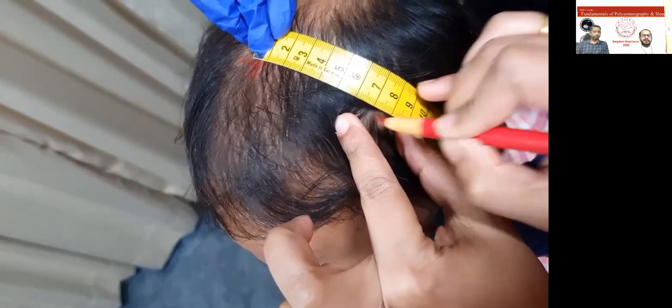As you can see, the total distance was roughly 38 centimeters, and 20% of 38 centimeters will be 7.6 centimeters. So from that initial intersection point Cz, we will measure 7.6 centimeters and use a small sketch pen to mark that location. This is as per the 10-20 system which was covered. So we will measure and mark all those points so that we can place electrodes on top of those points later.